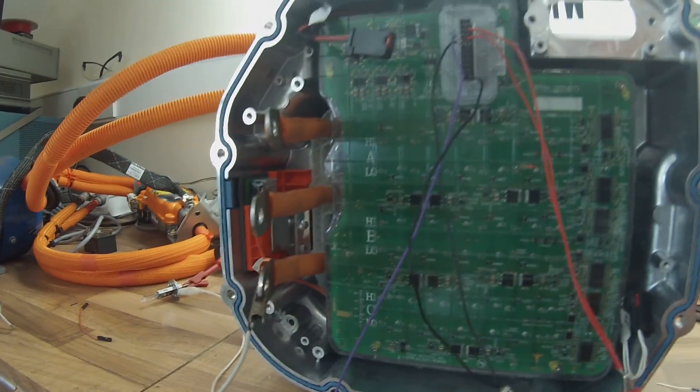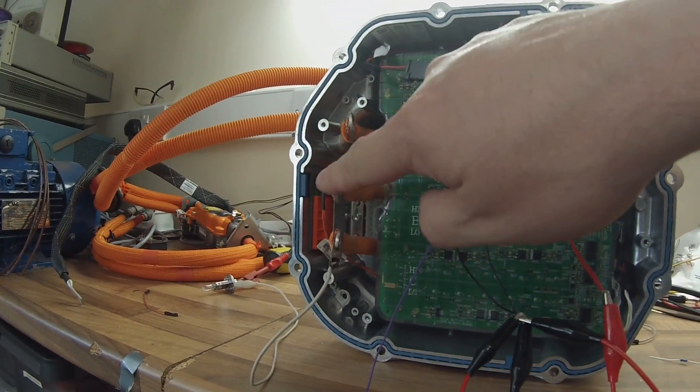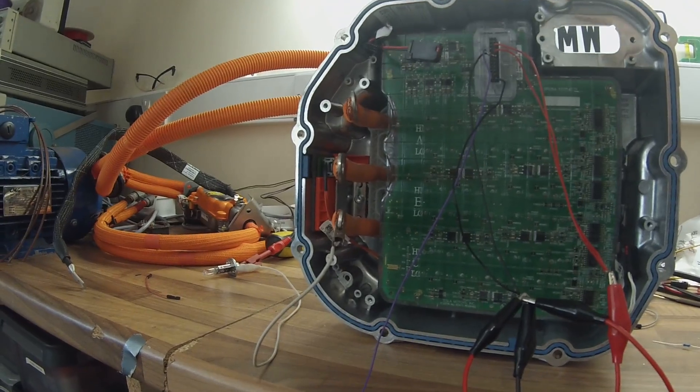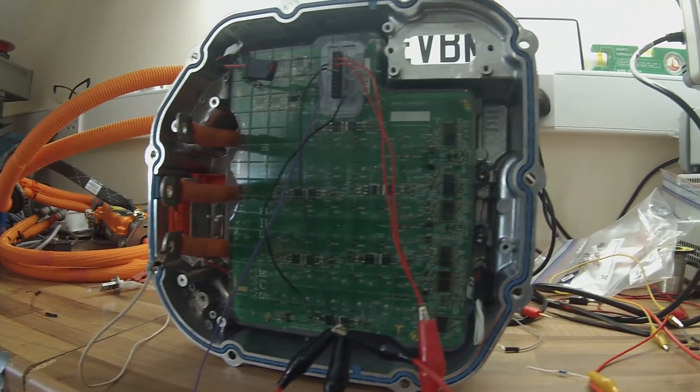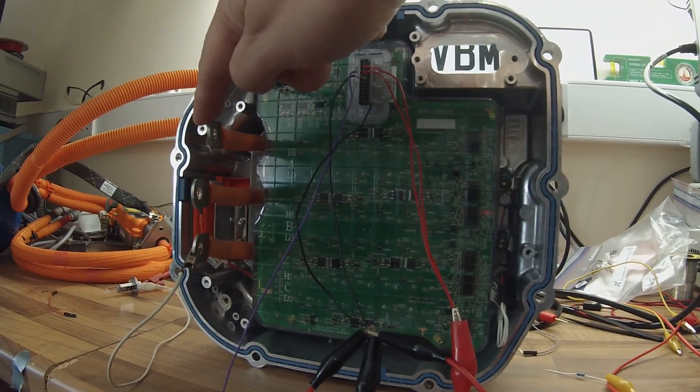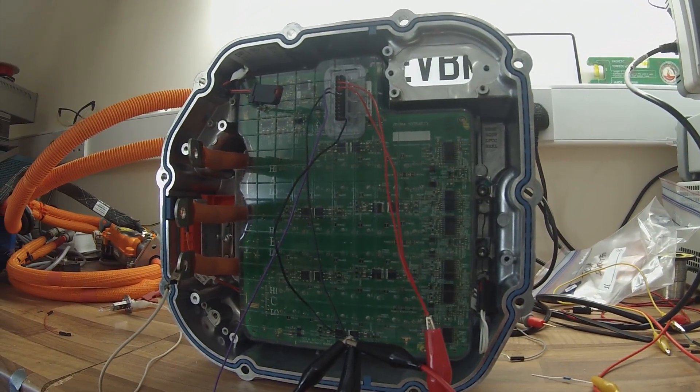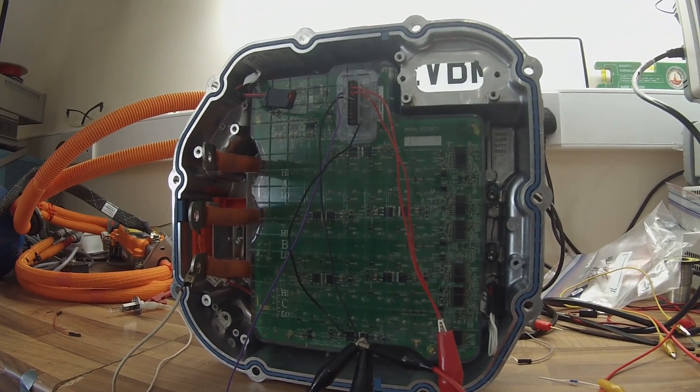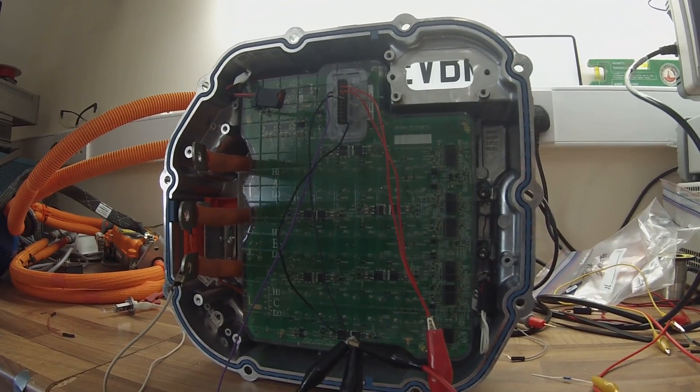Then it's just a case of repeating that for the three low sides and then swapping the power supply around to send the power in on the positive and come back out through the phase lines to identify the high side. So that's where we're at from an IGBT drive perspective.